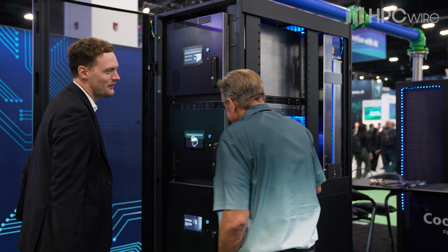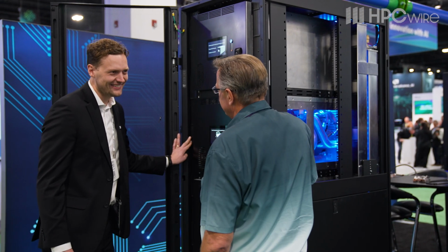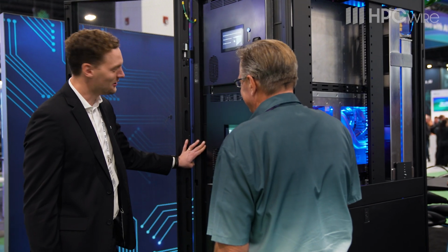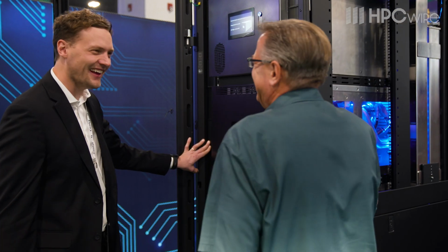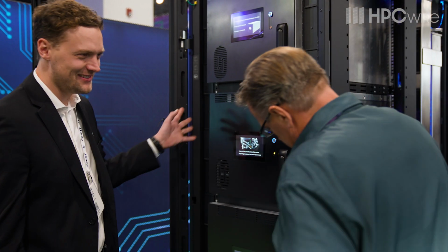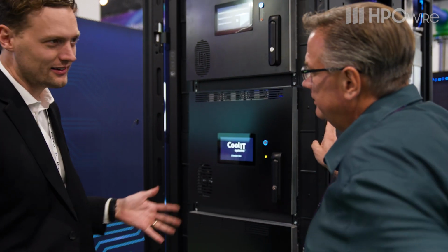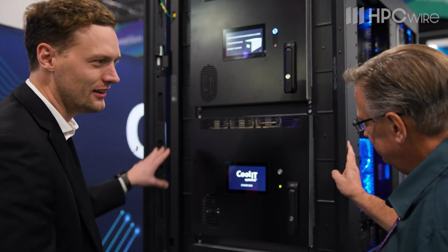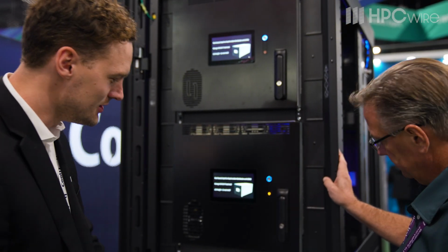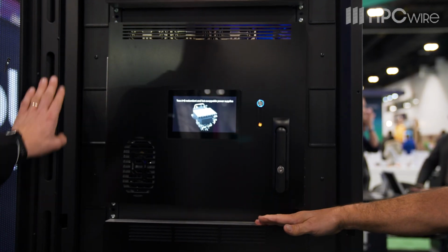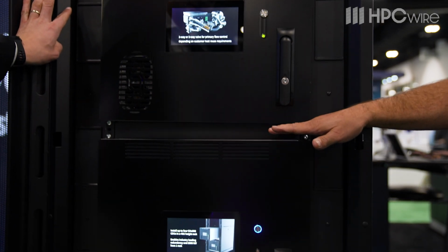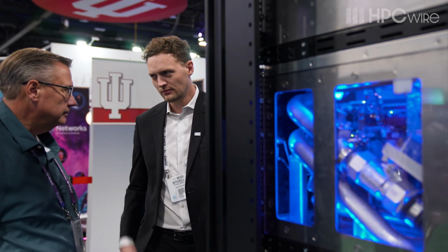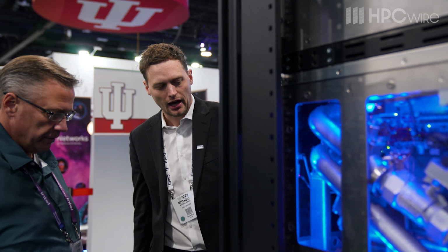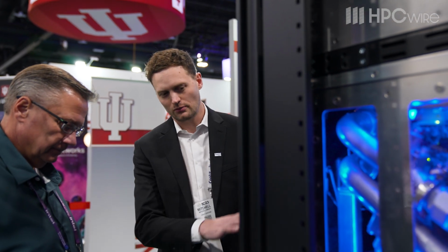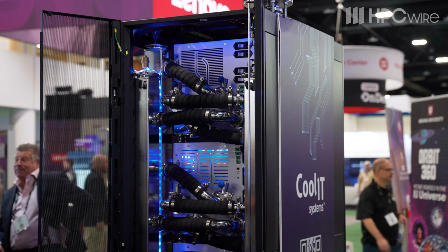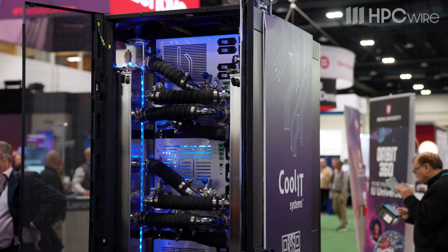The other one we're really excited about is our CHX500. This is a new product we're launching to market — a modular rack-based CDU that can be stacked up to 2 megawatts of cooling in a single rack. It fits in a standard IT rack, allowing customers to achieve a density with coolant distribution units the market hasn't seen yet. It's redundant, so you can put up to 4 units in a rack — maybe you only need 3 to cool your IT system, with the other as an extra unit if one has to come out for maintenance. The capacity and density of that unit is absolutely incredible.